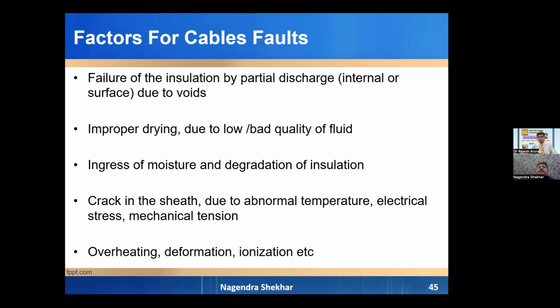The factors we have shared already. The internal factors, beyond damage to the cable, are partial discharge, either internal or surface, due to voids in the insulation; improper drying of joints while making epoxy joints, or bad quality of fluids; ingress of moisture and degradation of insulation because of any puncture or manufacturing defect; and cracks in sheaths due to overloading, electrical stress or mechanical tensions.